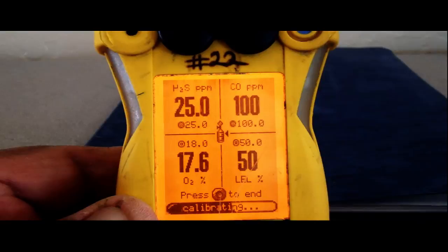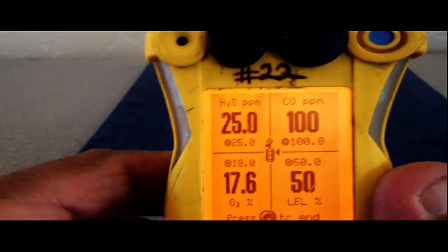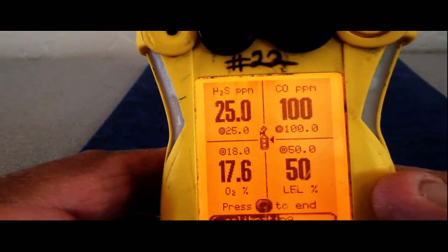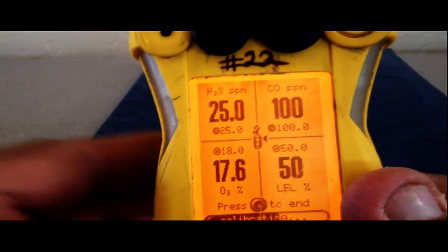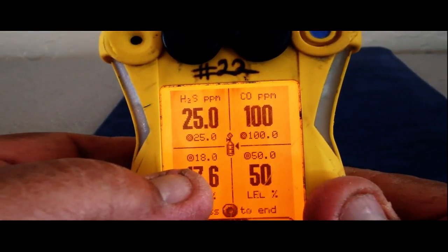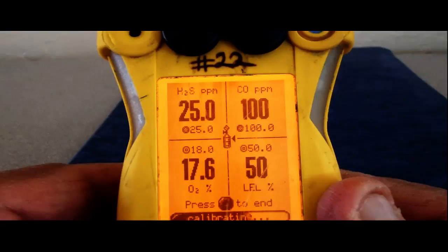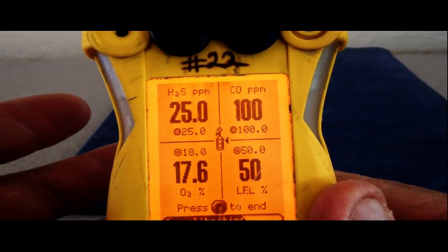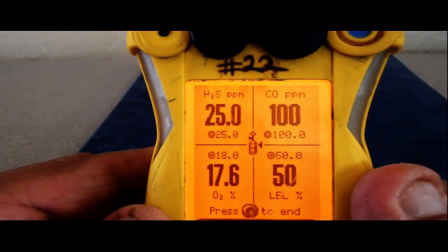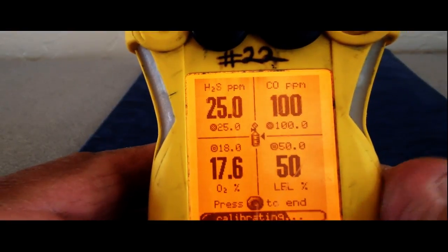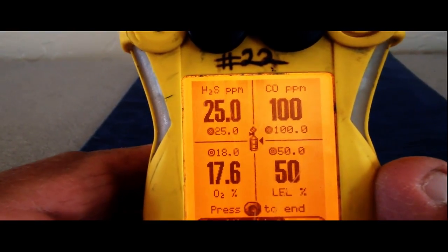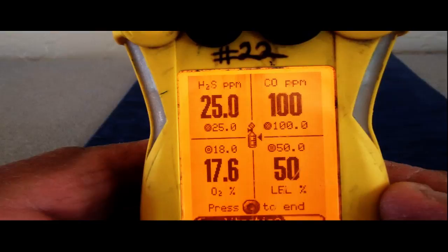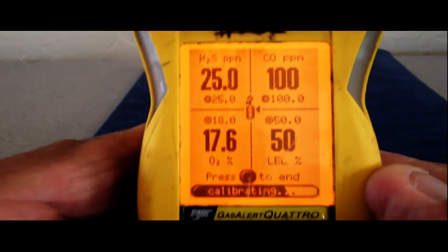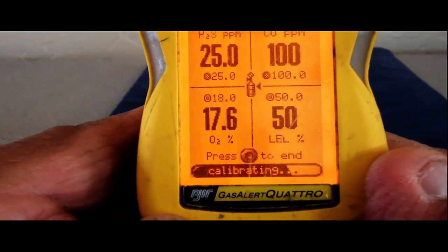I was once posed a question: when you're calibrating these units, what happens if that oxygen concentration is low? It's still going to perform when you get it out in the field. If that O2 sensor is bad, it will give you a bad sensor indication, and there's not a thing you can do about that. You're just going to have to change that sensor out, or send it in and have a qualified technician change it out.